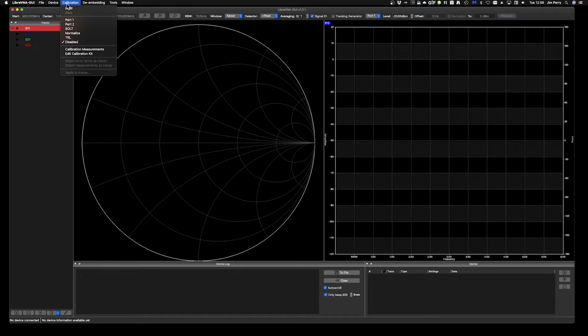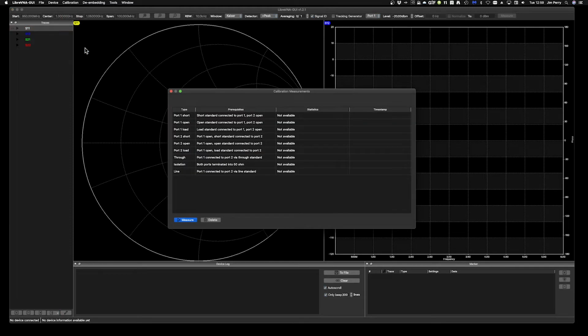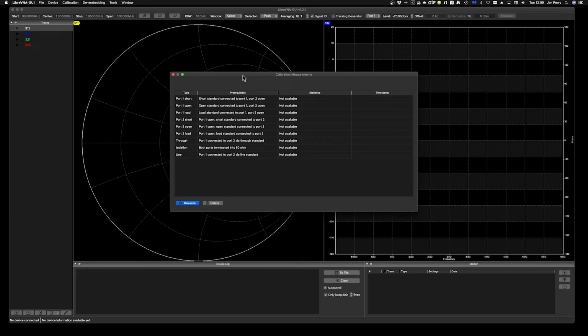I can do my calibrations just like you do them on a Nano VNA. I come down here and I tell it calibration measurements. It'll bring up this screen here, and it'll show that there's no info available because there's no calibration loaded. So I come down and I click which one I want to do. Let's do the port 1 short. It tells me what the prereqs are, that I need a short standard connected to port 1 and leave port 2 open. I click measure. It makes the measurements. It saves the date and time and tells me how many data points it used to do that calculation. And then follow through for all the other calibrations you may or may not want to do.